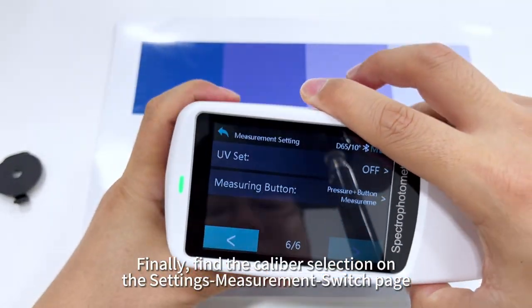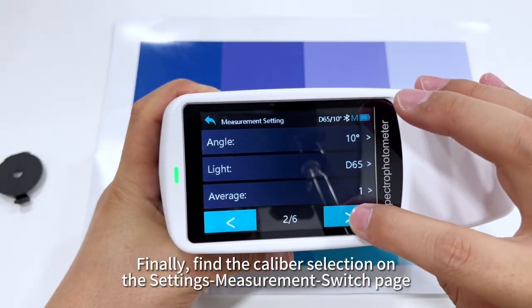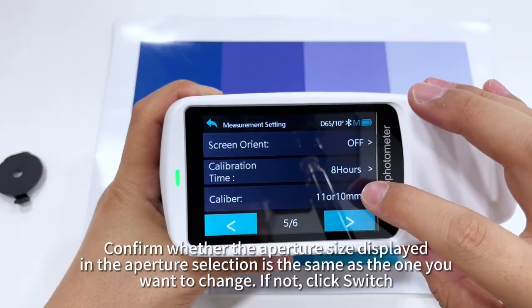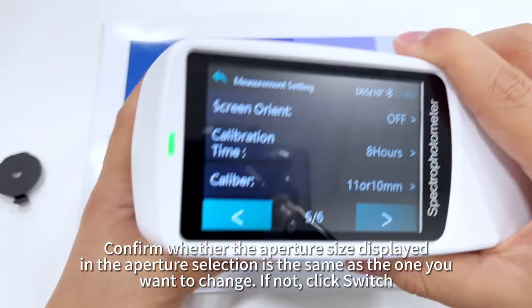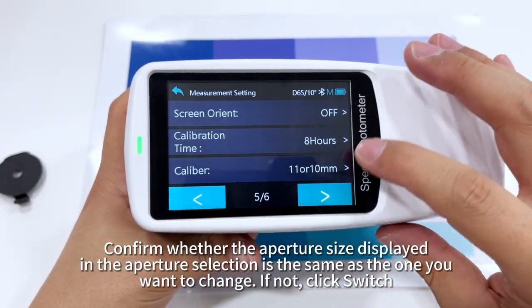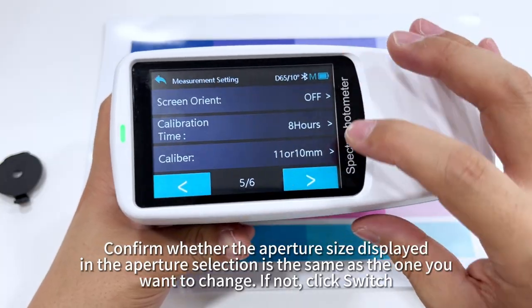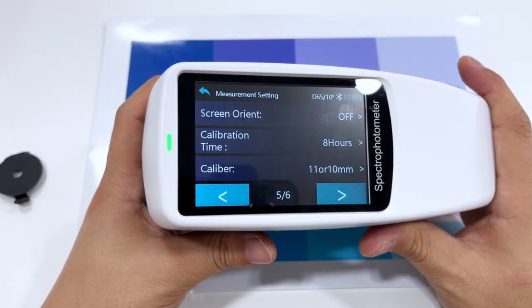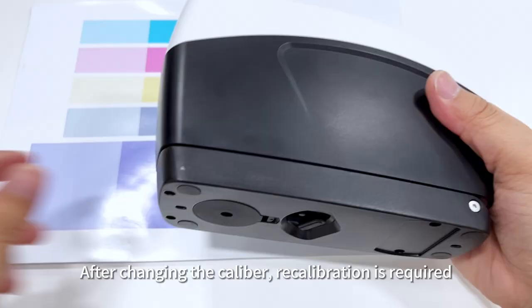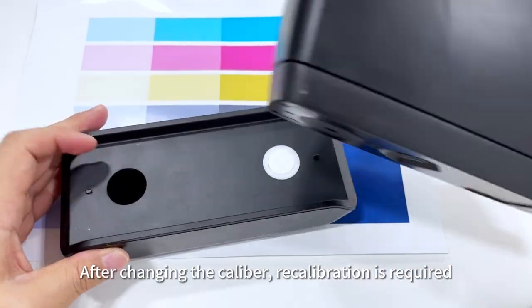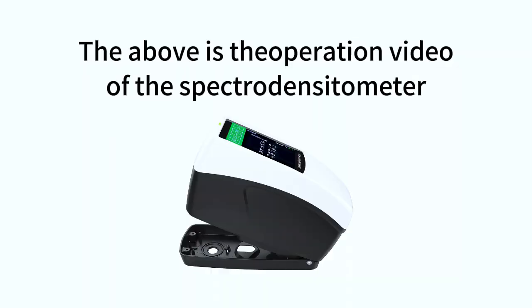Finally, find the caliber selection on the Settings, Measurement, switch page. Confirm whether the aperture size displayed in the aperture selection is the same as the one you want to change. If not, click Switch. After changing the caliber, recalibration is required. The above is the operation video of the spectrodensitometer.